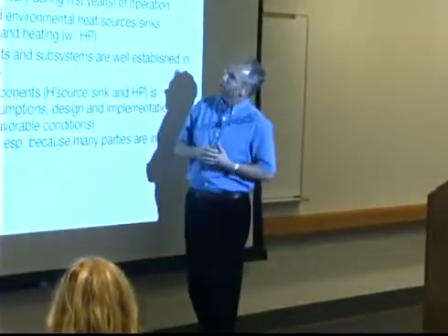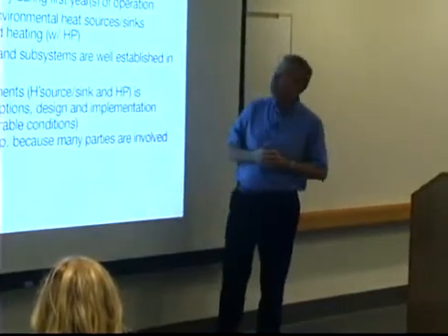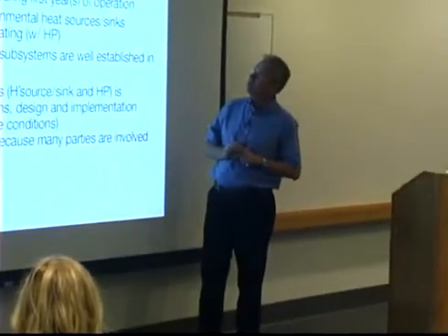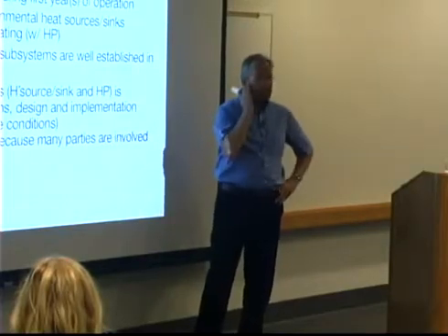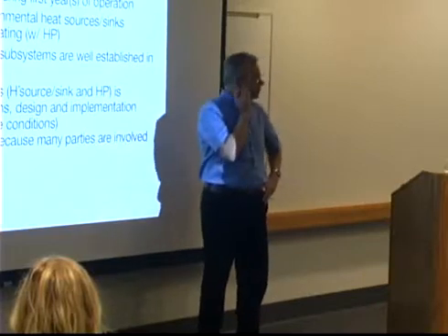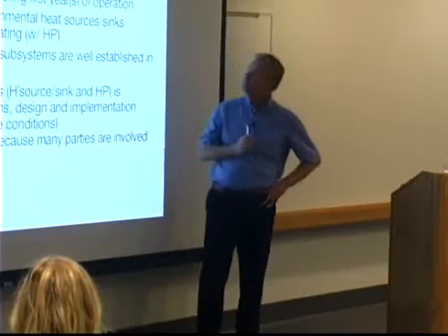Okay. So the conclusions we draw were that we can achieve these high primary energy performance or key performance indicators of less than 100 kilowatt hours of energy consumption. All these high performance buildings, all 19, showed that commissioning was necessary during the first 1 to 2 years, at least 1 year of fine-tuning the buildings before they worked well.